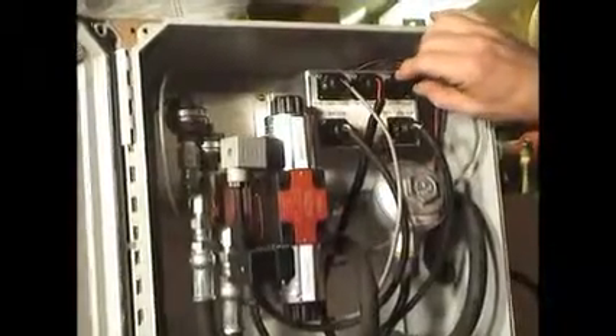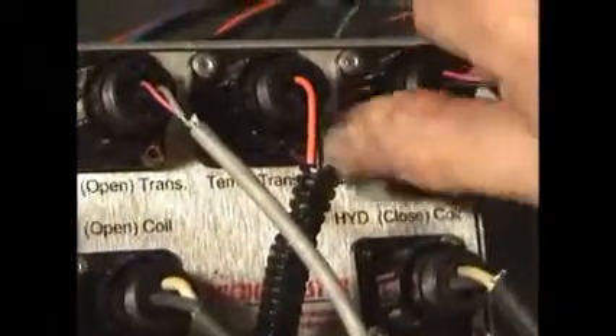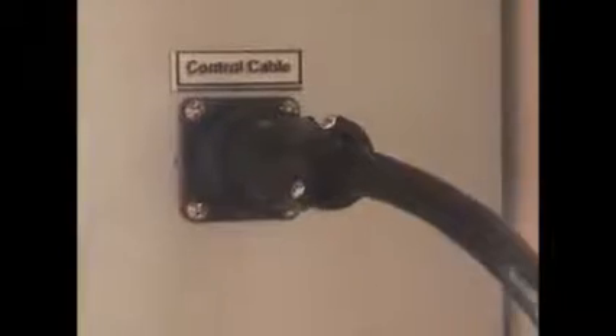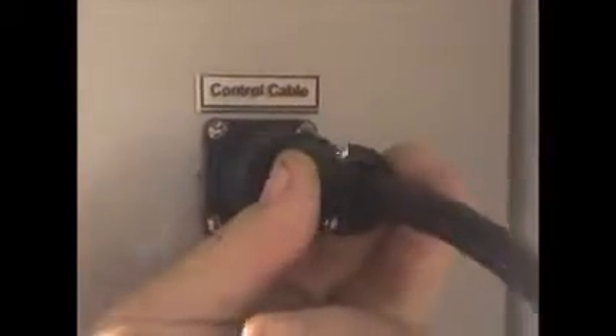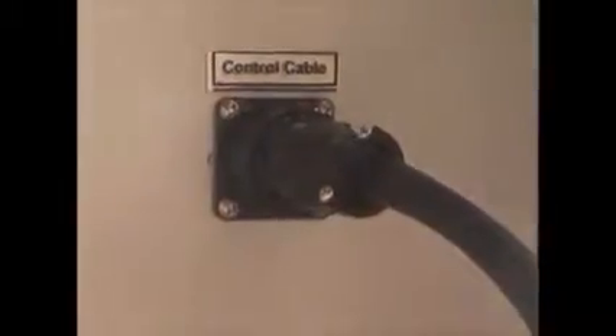And now I'm going to take the new transducer and install it back on top of the fitting. Okay, finish snugging up the fitting. Okay. I'm going to rotate the electric plug until it snaps in, and then continue to turn it tight. Removal and replacement of the main control harness is very simply done by unscrewing the nut and pulling it away from the unit. To reinstall the unit, you push it in until it snaps and continue to turn the nut in until it's tight.